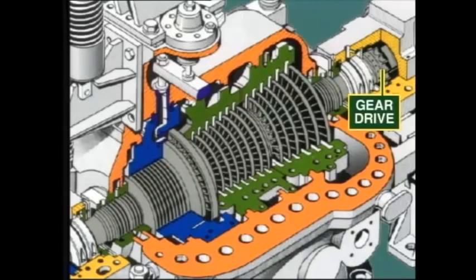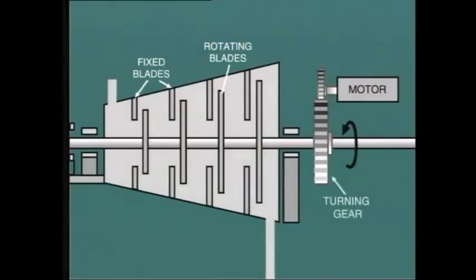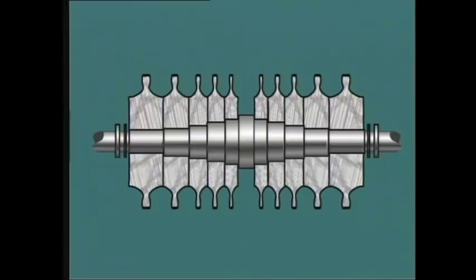the turning gear. As we'll see later, the turning gear allows us to rotate the rotor at very low speed, say 1 RPM, without having steam pass through the machine. This is used during shutdown to ensure even cooling and so prevent distortion of the rotor. More about this later. In earlier machines, the discs are shrunk onto the rotor shaft.